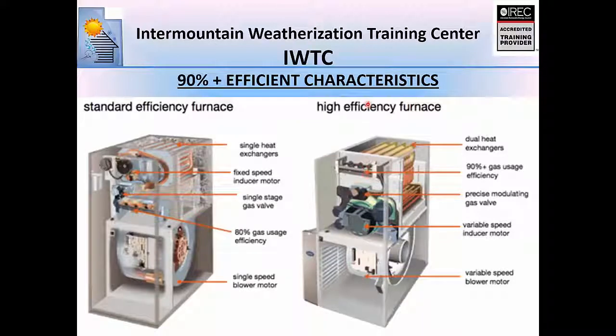So here are some differences that you'll note. One of the key things I want to point out is, notice over here, this is a standard efficient furnace, or anything less than 90%. Notice where the burners are located on this. They're located down low, so the flue gases have to move up through the heat exchanger and then out the flue. In all 90% furnaces, in order to help with heat extraction and get more contact time with the air, the burners are up on the top.